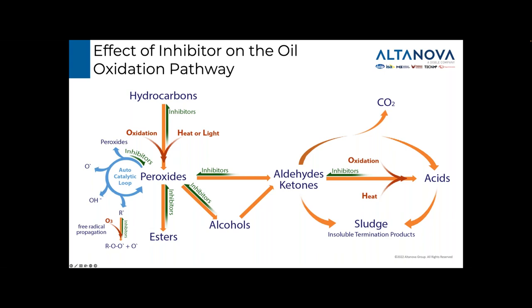Natural and synthetic inhibitors work in the same way to stabilize the oil, and as can be seen in the above diagram, the inhibitor counters many of the degradation pathway steps, meaning the oil oxidizes much more slowly and is more resilient to heat. Knowing if your oil is inhibited or not is important to ensure the correct oil type is used to top the oil up to prevent dilution and reduction in efficacy of the inhibitor already in the oil.